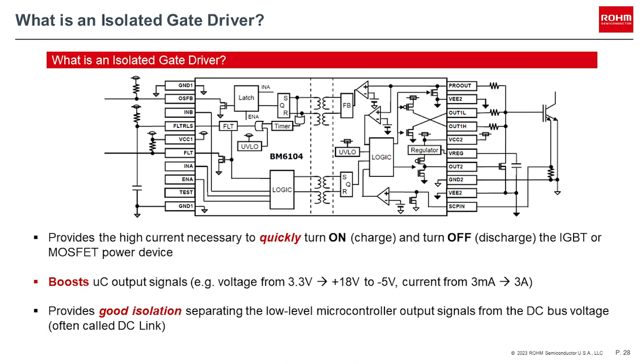Secondly, providing the high current necessary to quickly turn on or charge and quickly turn off or discharge an IGBT or MOSFET power device. Lastly, delivering good isolation, separating the low-level microcontroller output signals from the DC bus voltage, often called the DC link.